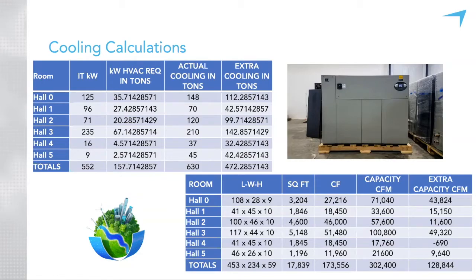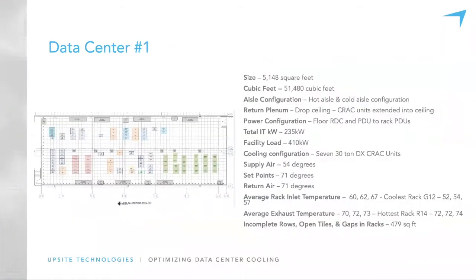We're going to look at some of these data centers and we'll see that we don't just put all our equipment in one area of the data center, that it's spread out. The CRAC units, we do have to take into consideration not only the supply air, but if we have any type of plenum or any return for the hot air to go back, we have to consider the cubic feet distance and volume associated with that as well, so we can move both the supply air and the return air effectively. So again, these 2 charts will give you a great idea on how to size by kilowatt and also by cubic feet. All right, here we go, real life data center scenario.